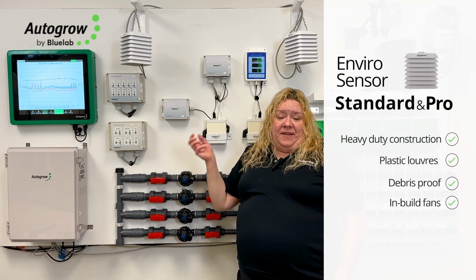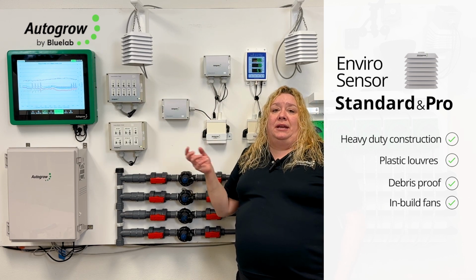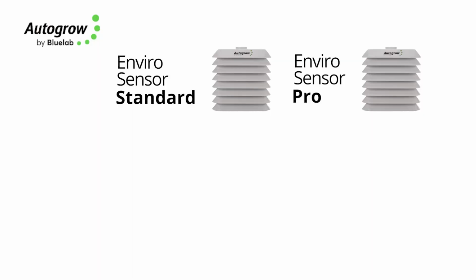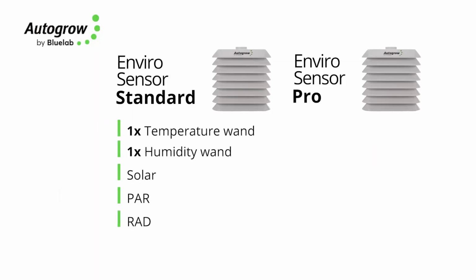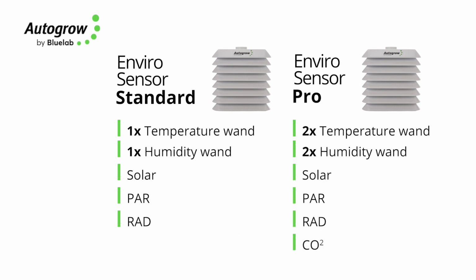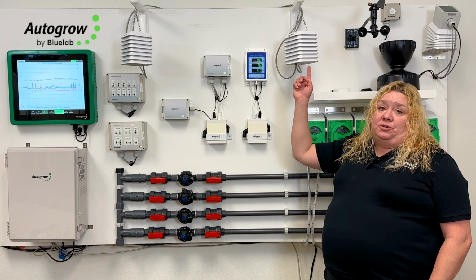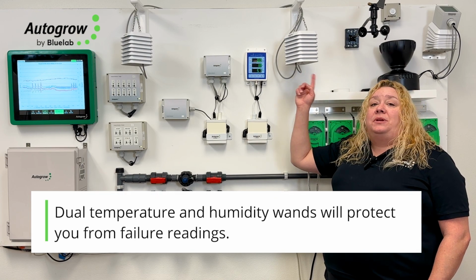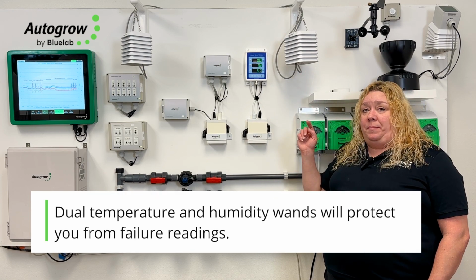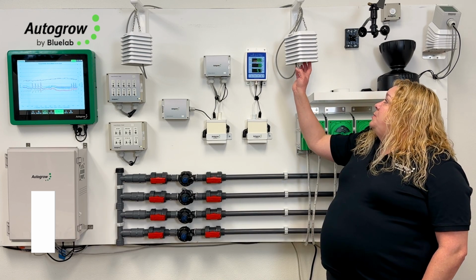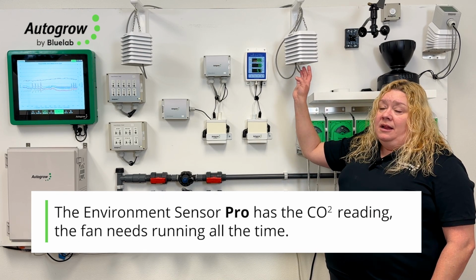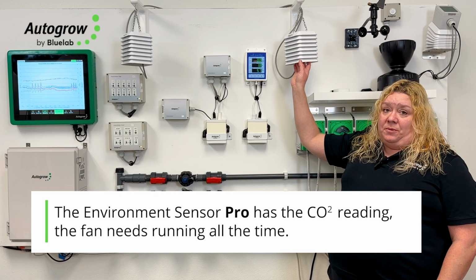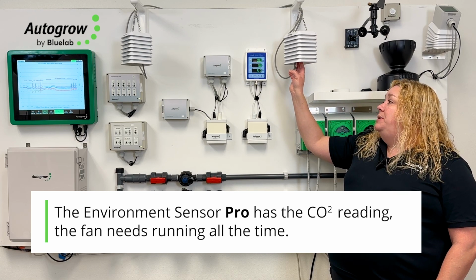They have aspirated fans inside of them so that we make sure that we're getting a really good reading. The standard sensor has one temperature and humidity wand, where the Pro sensor has dual temp and humidity wands. The reason that's important is redundancy: if one of the temperature and humidity wands were to fail, you could default to the other until you could swap it out. Now, this one also has the CO2 in it, so it's important that the fan is always running in here to make sure that we're getting good CO2 readings.